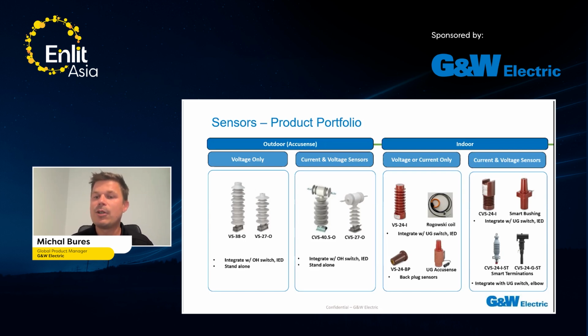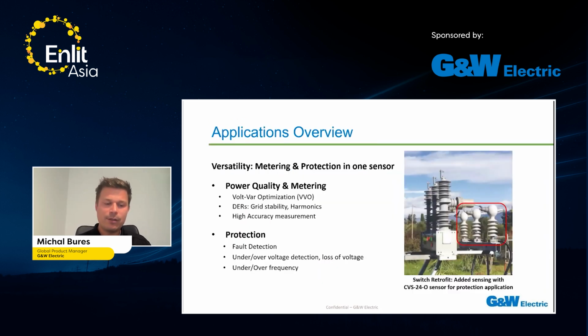Plus, we have smart terminations, an amazing solution, so you can integrate the smart function directly into the cable, so you can measure current and voltage at the same time. This is amazing. So with our sensors, as I mentioned, you have metering and protection in one body, so you can connect to the protection relay, the energy meter, the power quality analyzer, even advanced ones, right? So the most common applications are power quality and metering, volt var optimization, measurement of the DERs, as I mentioned, the harmonics, and of course, high accuracy measurement. We can use it for fault detection, for under/over voltage detection, loss of voltage, and under and over frequency measurement.